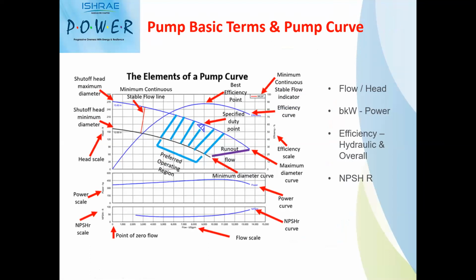When it comes to the basic terminology of pumps, the pump's performance or any parameters are referred to through the pump performance curves. So it is important for us to know the parameters or the terminology which is used for reading a typical centrifugal pump performance curve. This is a typical centrifugal pump performance curve where you can see this axis is the y-axis, which mentions the head values, and the x-axis mentions the flow values. Pumps are typically selected with the pump performance curves, wherein you can see this is the specified duty parameter of the pump. So any designer or any requirement for a pump will have to have flow and head. That flow and head is typically selected on a particular pump curve, which is called the specified duty point.